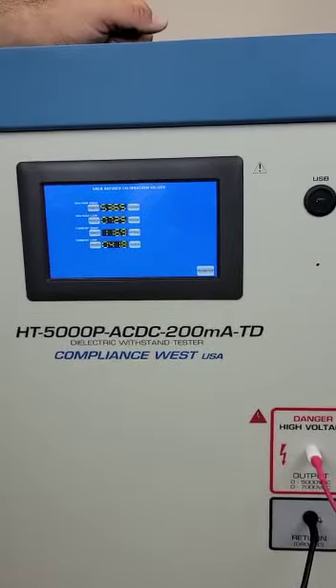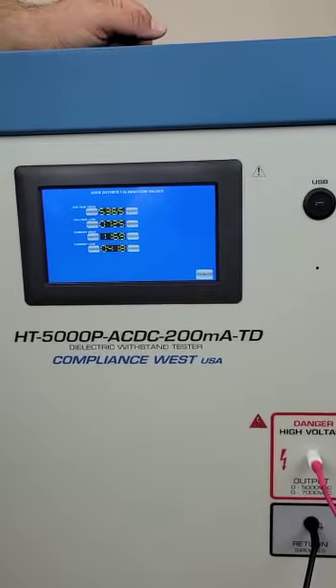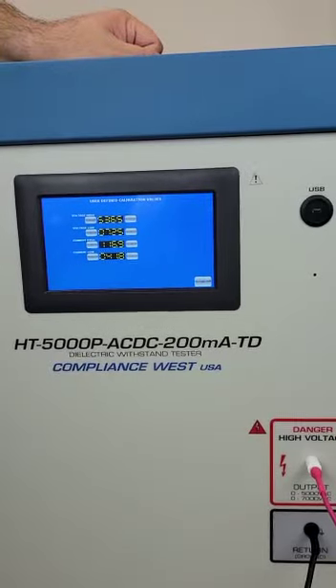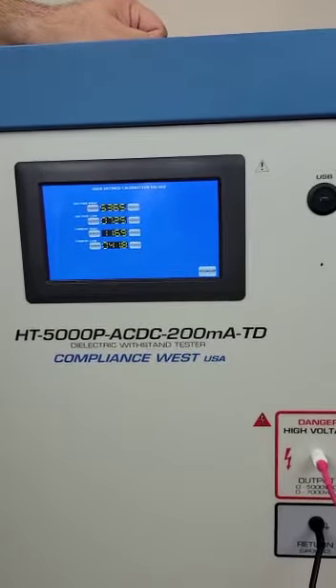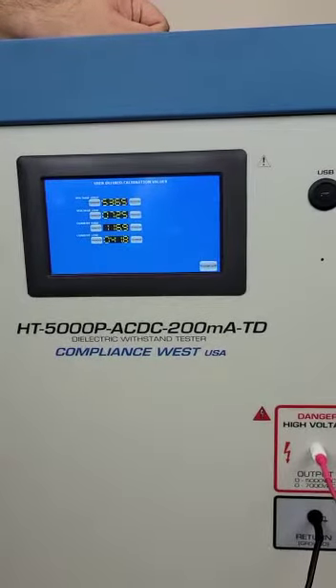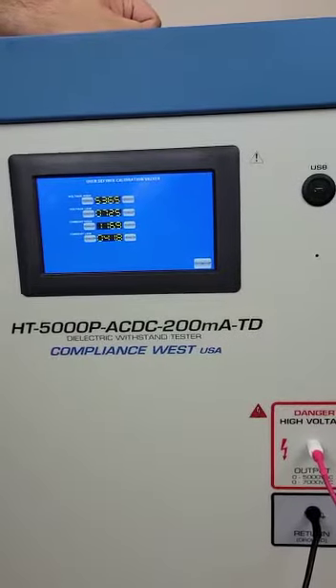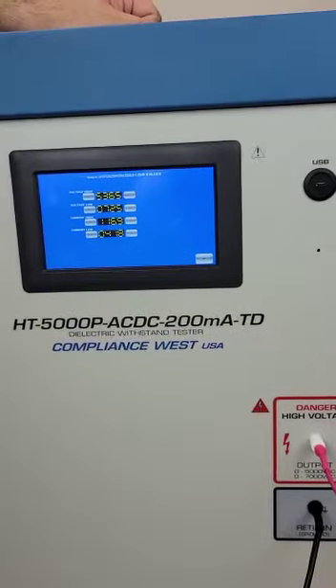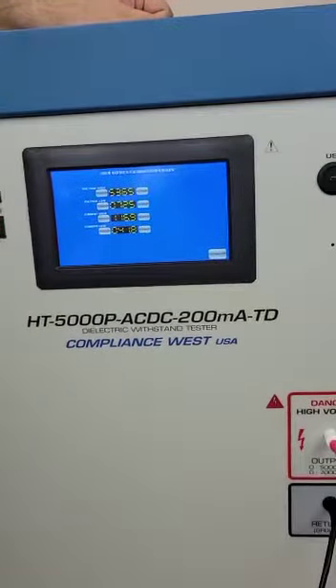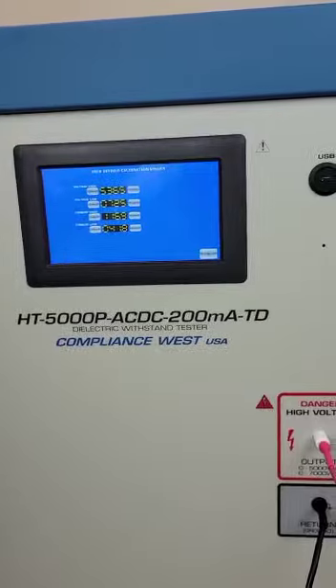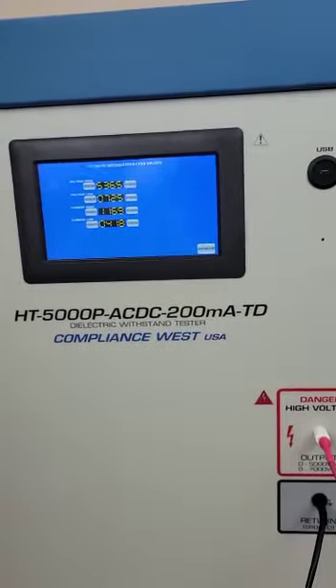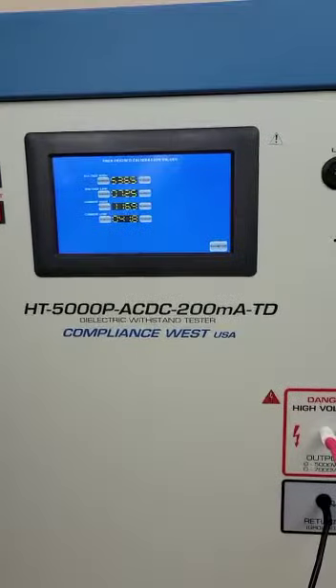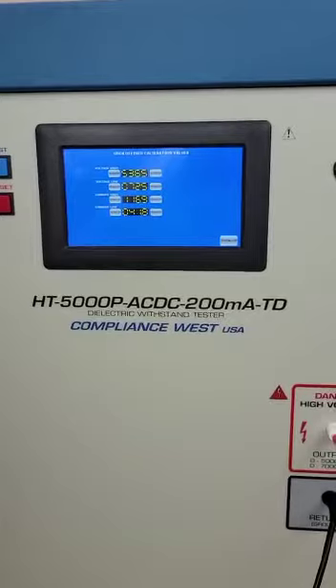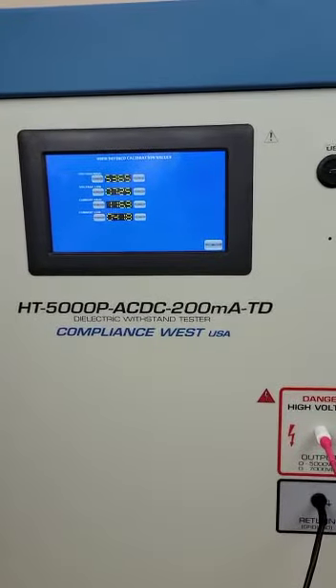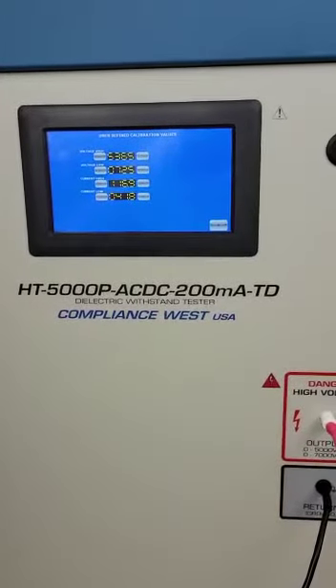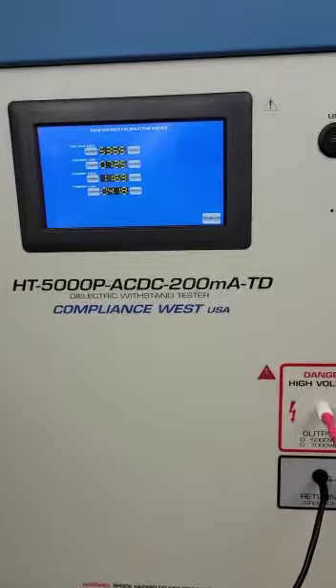The same process applies for the leakage or for the current. You need to set up the load so you can flow at least 120 milliamps. We recommend points of something around 40 milliamps and 120 milliamps for calibration purposes. You gotta make sure that your load can handle the power, and you can calculate by Ohm's law what resistor you want to use to make sure you can flow the current.